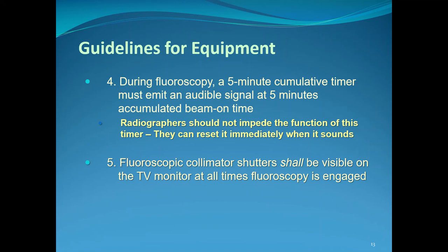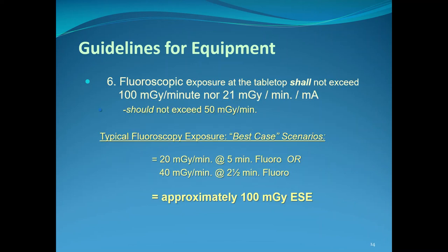Fluoroscopic collimator shutters shall be visible on the TV monitor at all times fluoroscopy is engaged. Lastly, fluoroscopic exposure at the tabletop shall not exceed 100 mGy per minute, nor 21 mGy per minute per mA. Fluoroscopic units operate at very low mA — single digits — with longer exposure times. Typical fluoroscopic exposure scenarios: 20 mGy per minute at five minutes of fluoro, or 40 mGy per minute at two and a half minutes of fluoro — both adding up to approximately 100 mGy total entrance skin exposure.